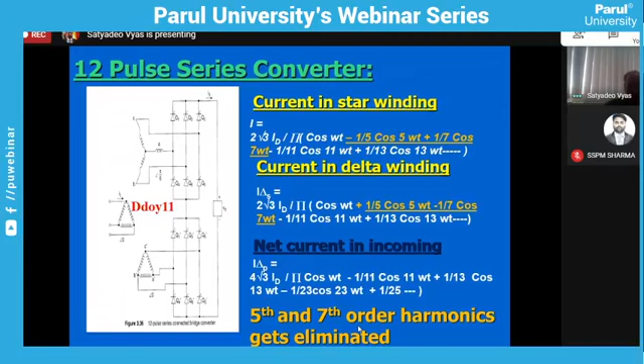Second, these harmonics also disturb the motor torque. Harmonic number: if we see 1, 2, 3, 4, 5, 6, the phase sequence, positive phase sequence is the fundamental component. If we are feeding the phase sequence R Y B, with current in phase with voltage, that will create a positive torque, or the phase sequence will be plus. Second is the minus. If it is R B Y, if the phase sequence is reversed, it will generate negative sequence. And third is zero sequence harmonics. So when the second order torque or phase sequence is present, the net torque will reduce.